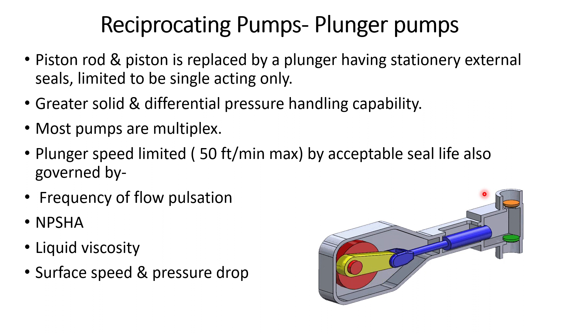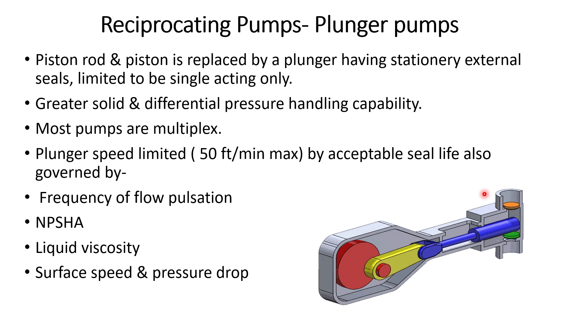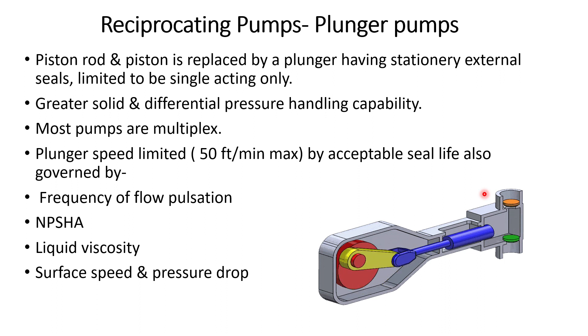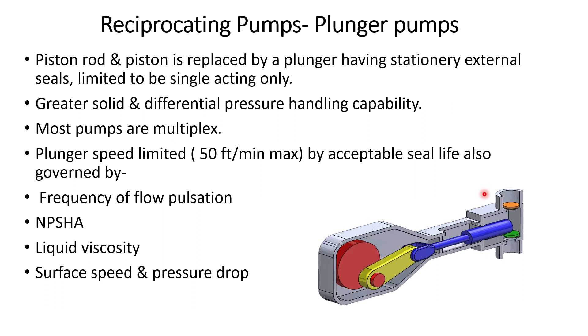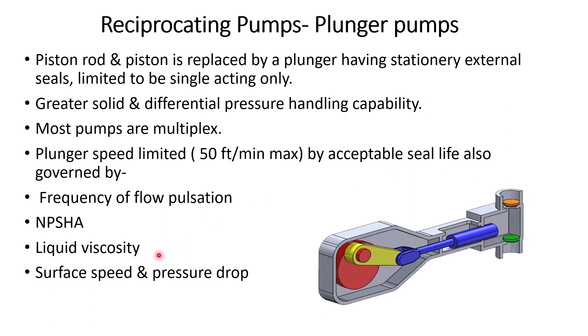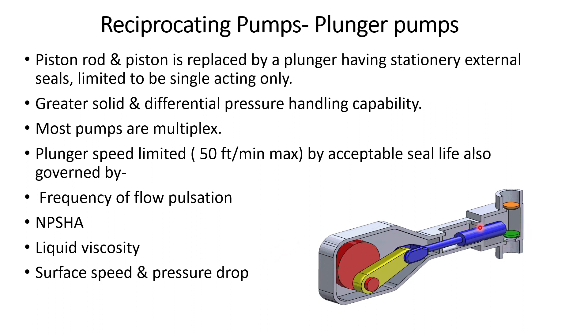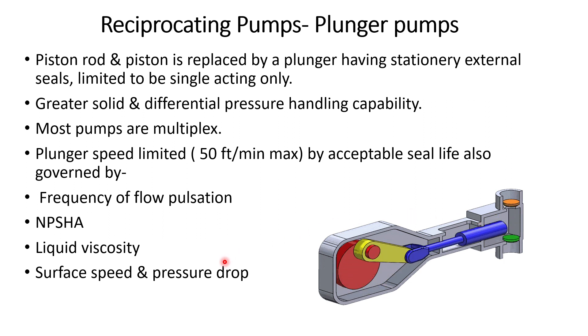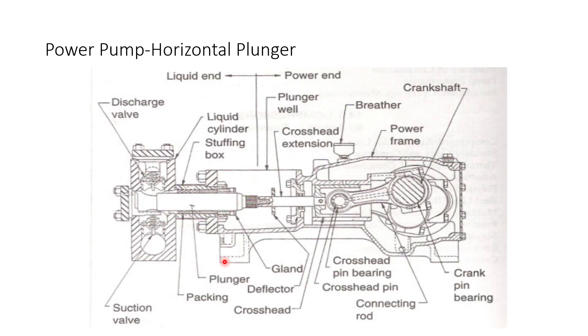The pumping speed is limited to 50 feet per minute maximum. The acceptable seal life is also governed by the frequency of flow pulsation, the net positive suction head available, the viscosity of the liquid, the surface speed, and the pressure drop across the pump — which occurs due to leakage through the running clearance of the plunger from the discharge side to the suction side.